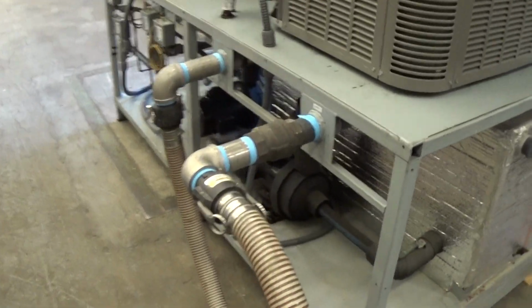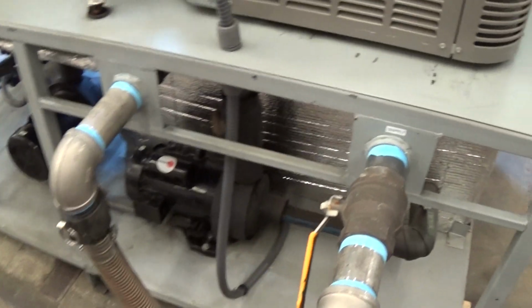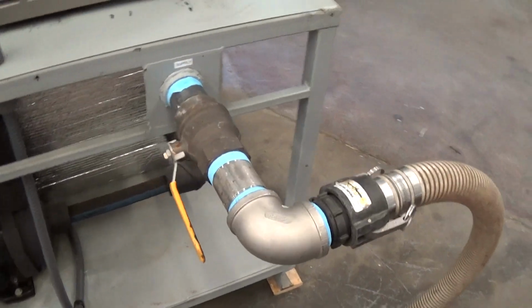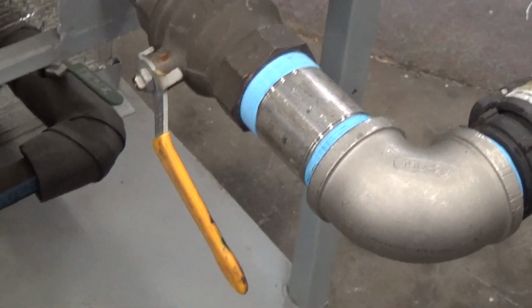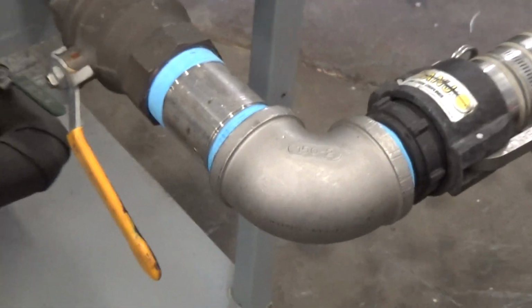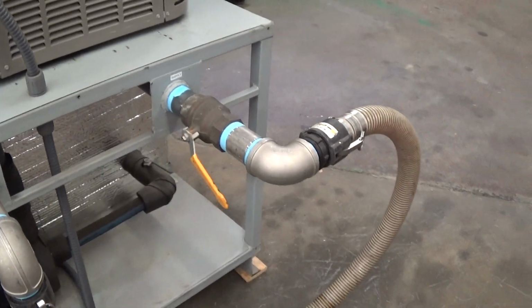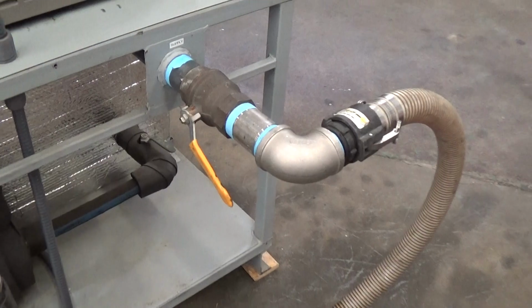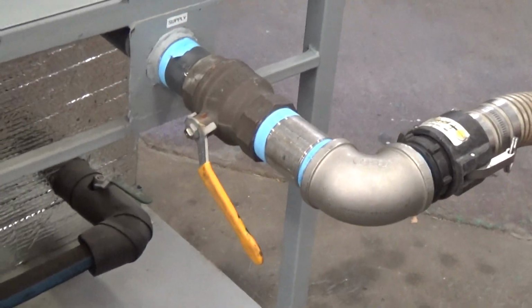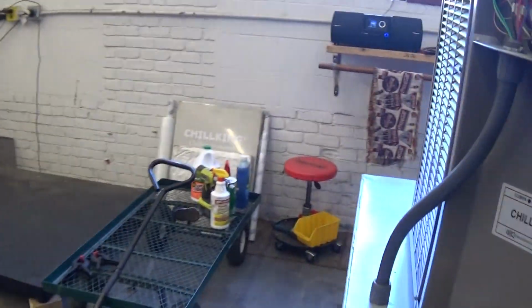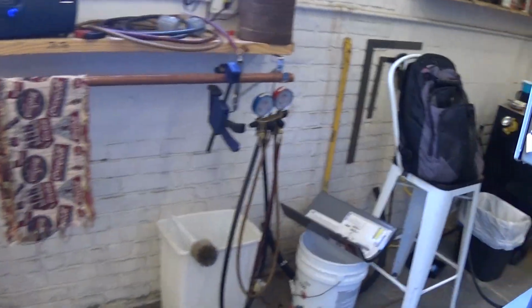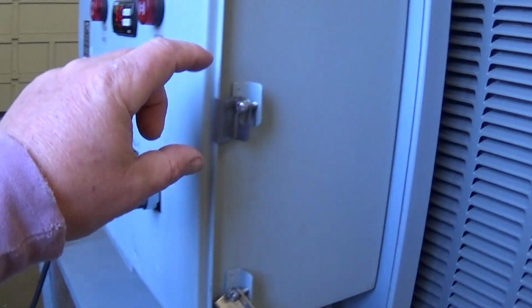But anyway, for our test, so the pump doesn't over amp, we have to throttle down the flow a little bit. That's our own valve we put on for the loop. A pump does like to have some back pressure. If I open that up full open, the pump would probably over amp, because that means the pump is spinning too fast.